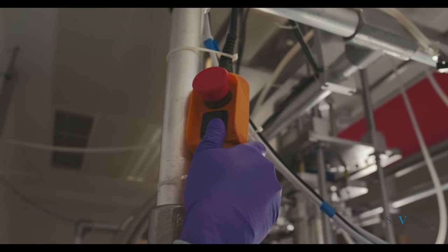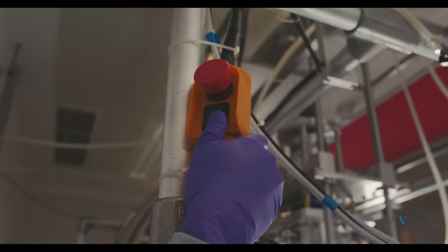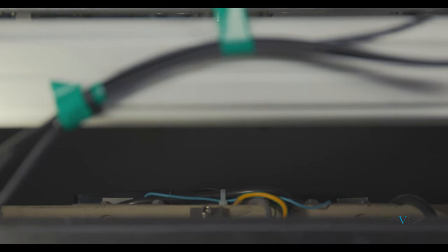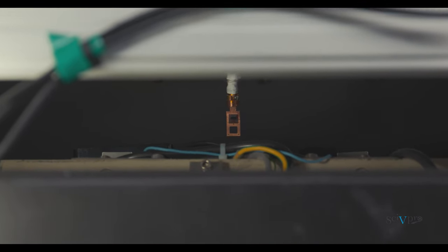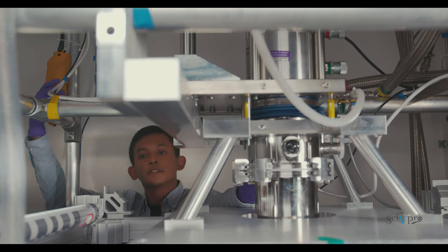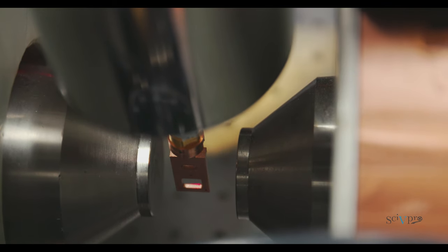Use the pendant crane control to bring down the sample until it is centered between the two electromagnetic poles. Use extra care to avoid collisions with setup components. This is the correct final position from outside, and this is the correct final position from inside.